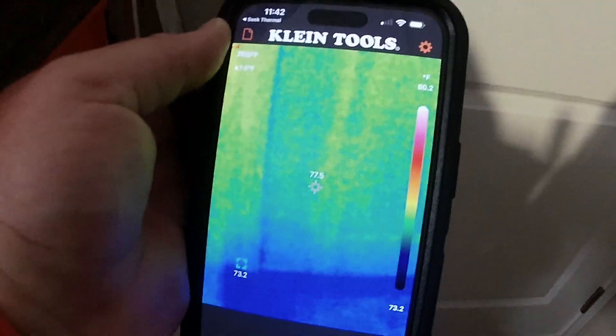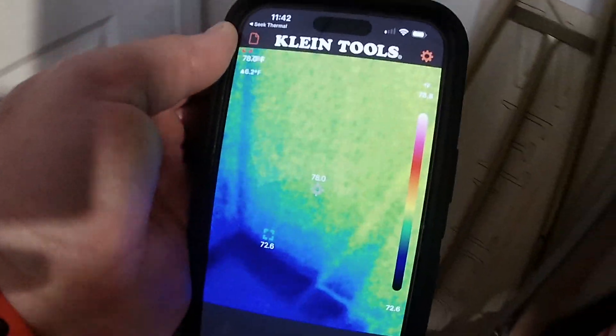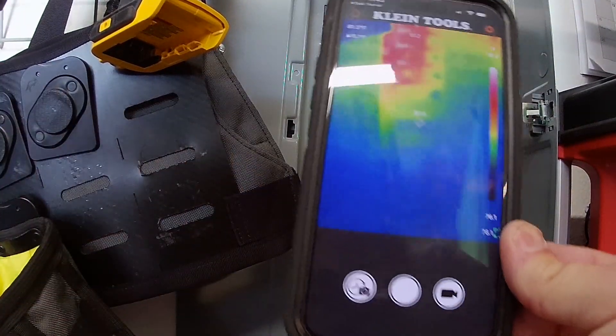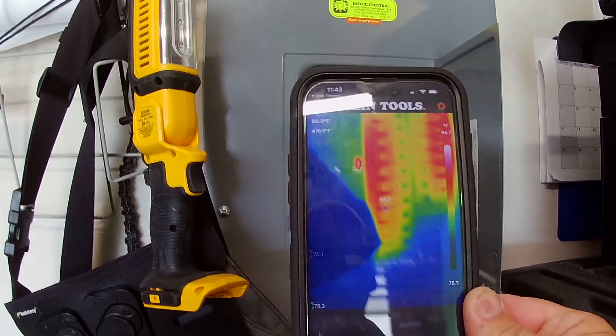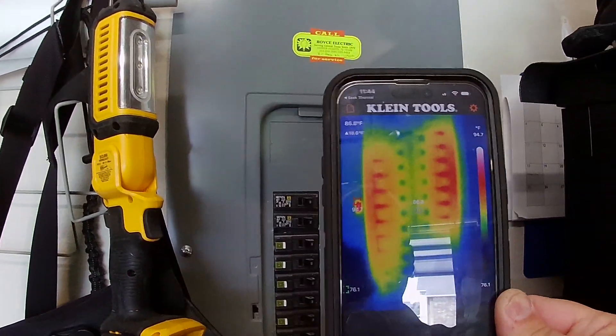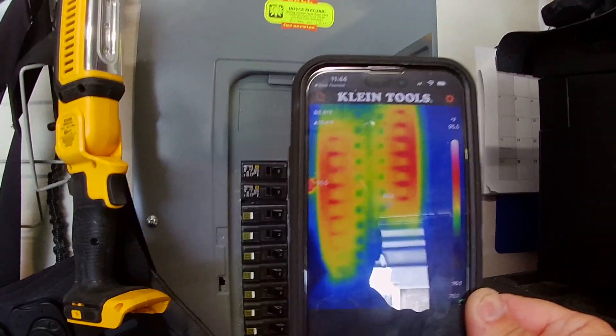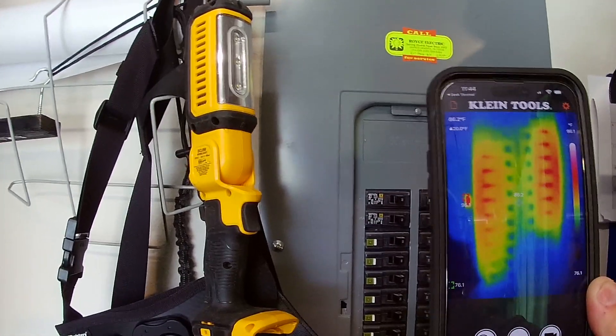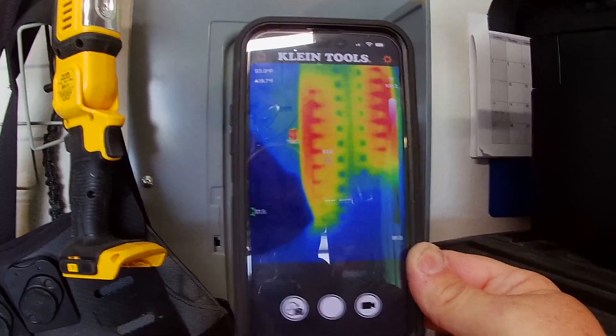I like the rainbow mode. I had my hand over the light switches — you can see it's showing 89, 87, 95 degrees. The Klein one is a little more responsive, plus it's a newer version. Checking the light switches down here — I have one set up as a timer so it has some LEDs in it. You just move the center of the screen around, which is the actual center of the camera. You can see the floor, a door, and then the wall. That's why I like Spectra mode. Now I'm doing the breakers again — most of them are around 88 to 89 degrees, pretty close to the Seek reading. They're both really good tools.